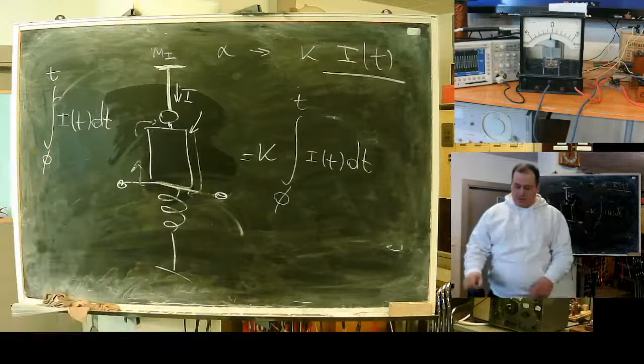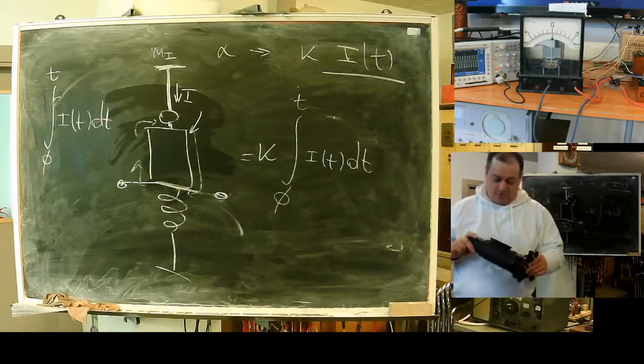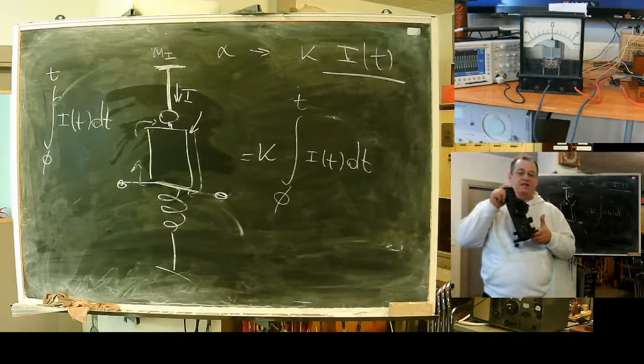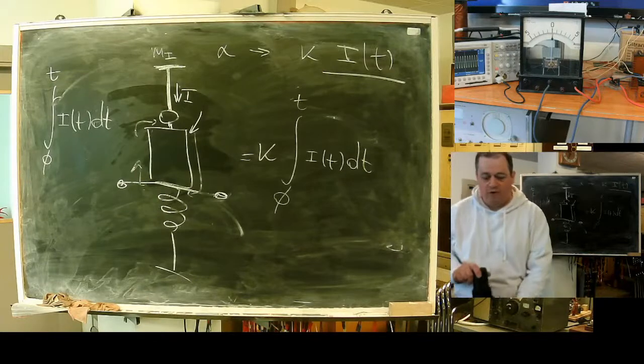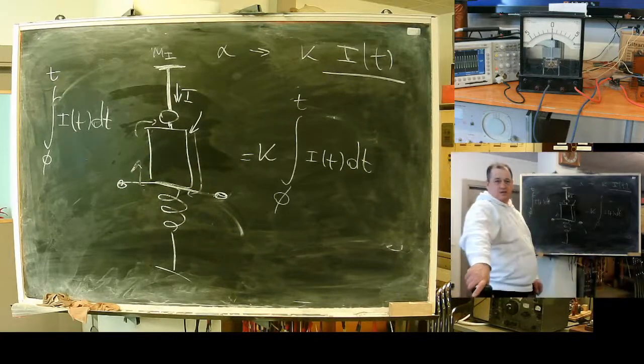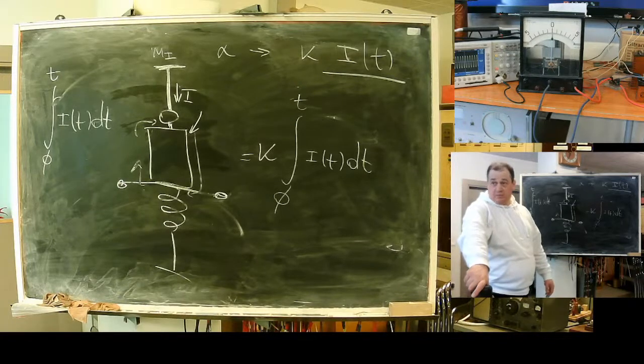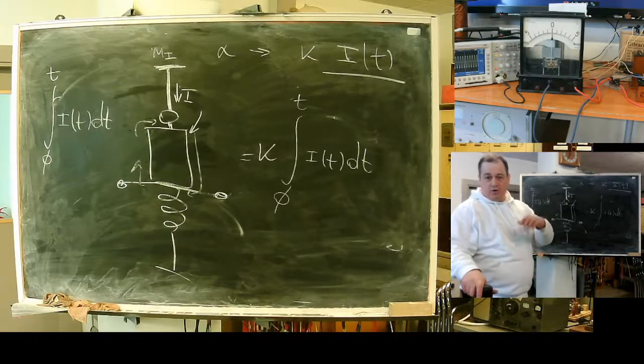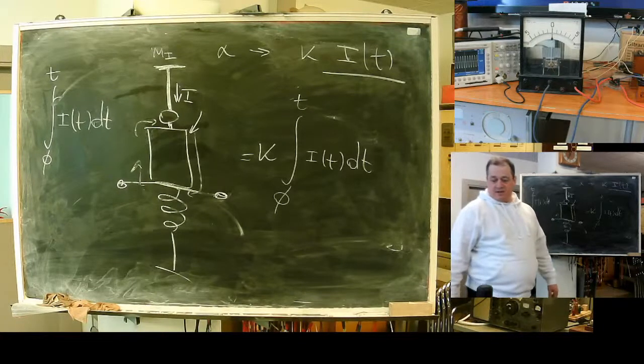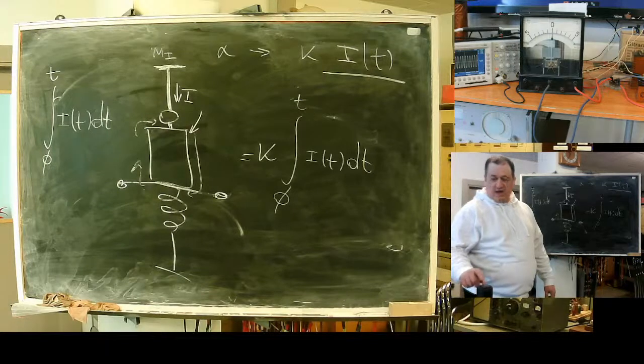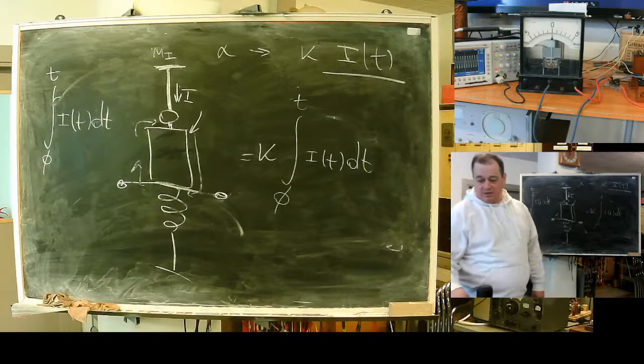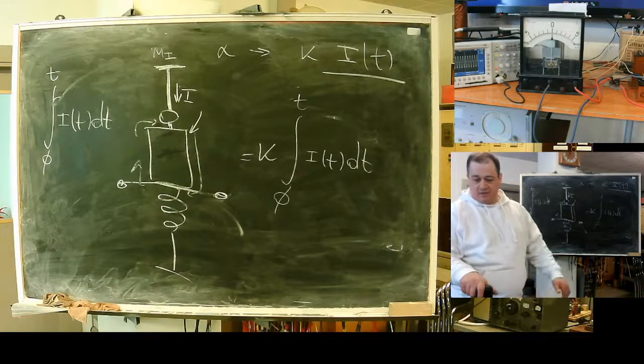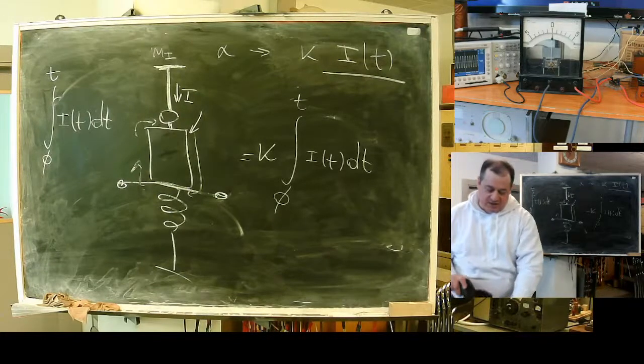Legends say these were produced during the Second World War, designed to catch German submarines. Coils were placed in narrows near the British coastline, and if a steel submarine, which has its own natural magnetic field, passed through the coil, the induced voltage was integrated by these devices. The key idea was that the time constant, this integration constant, was selected to prevent false triggers from small boats or something like this. Only a submarine large enough, integrating its magnetic current, would trigger the system.